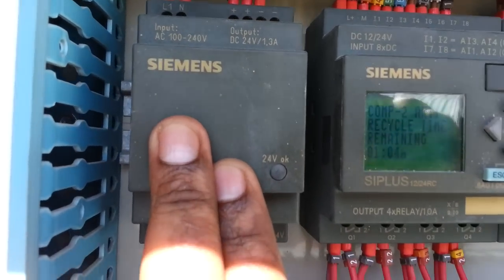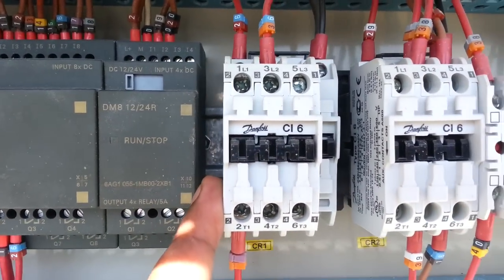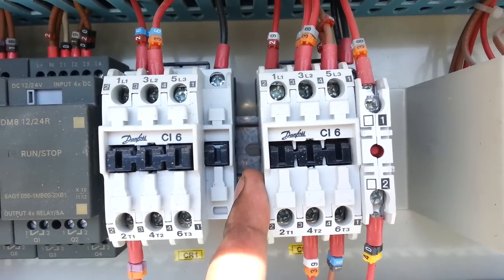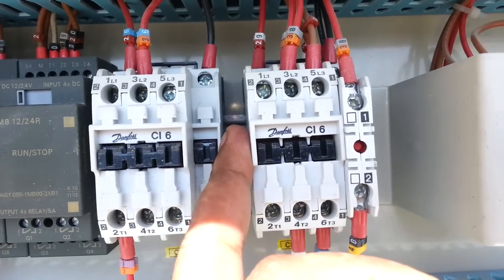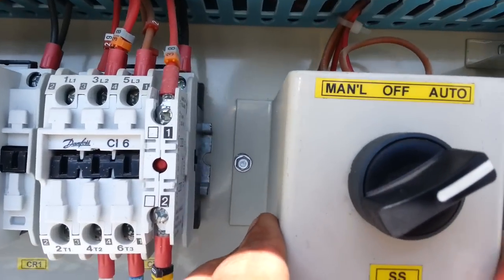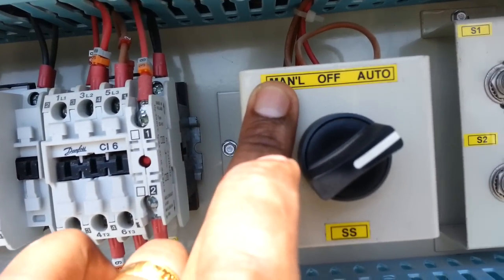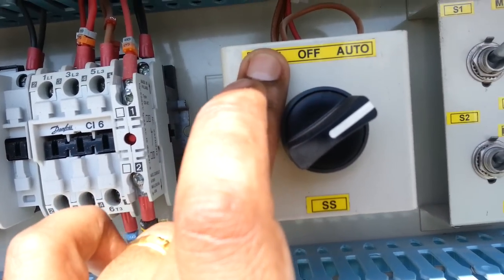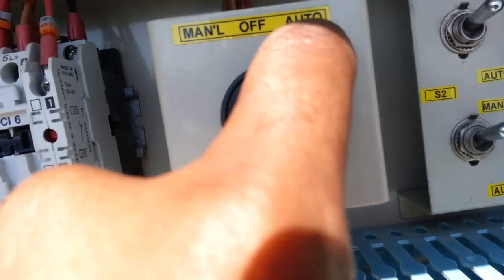This is the power supply, and here is the common fault relay. This one is for the power run status indicator. This machine works with the DDC panel. There is also a manual control — we can run it without DDC, which means it will work through the thermostat. In the auto position it will work in DDC mode.